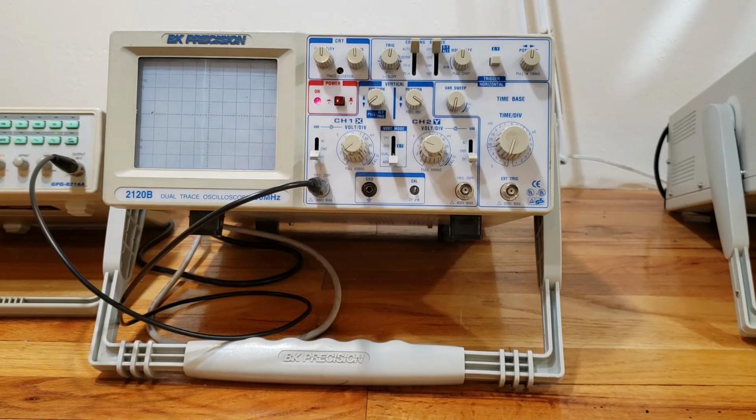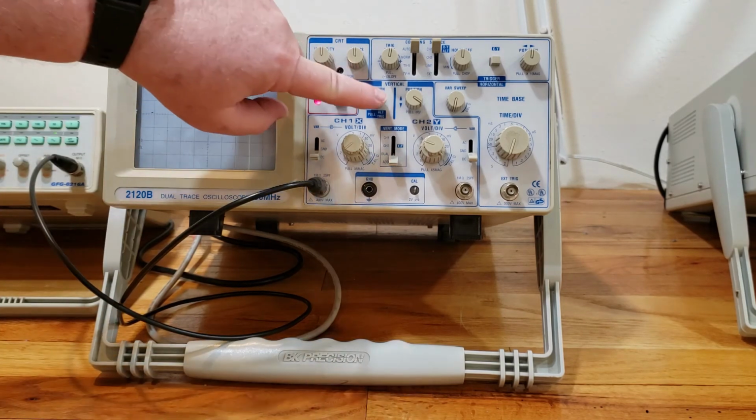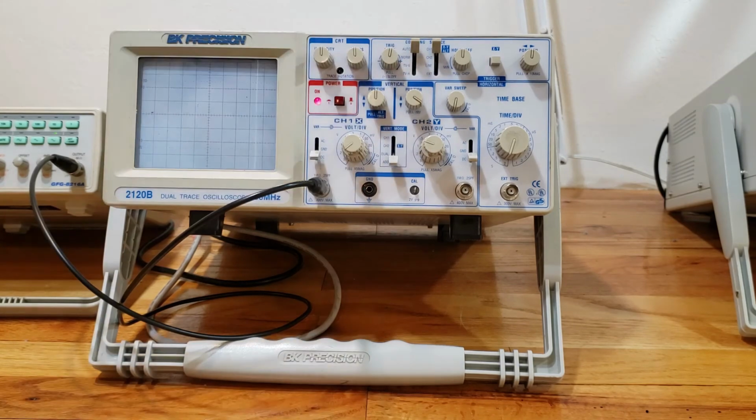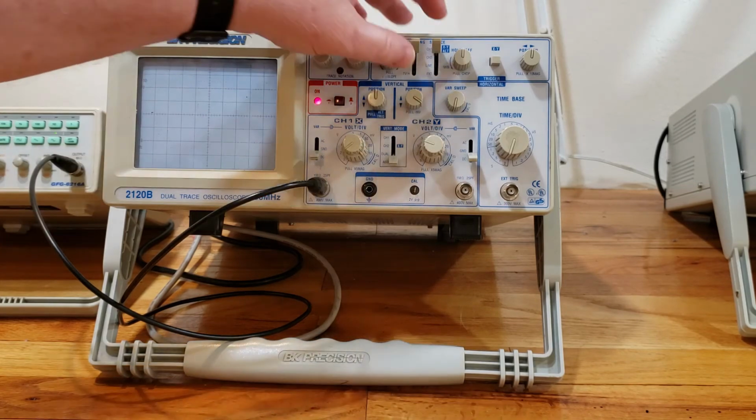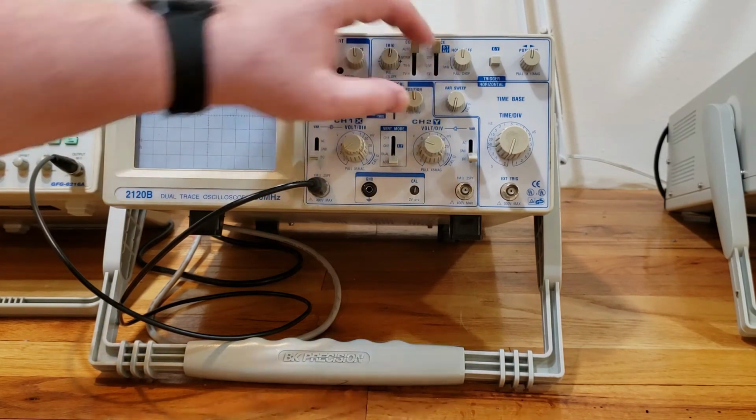Middle row, of course the power button, we're generally going to have that on, right? That would bring us to the vertical position knob for channel 1. Again, I'm going to do two things to the vertical position knob. Can you guess what those two things are? Yes, indeed. Pushed in and centered. Now, even though I'm not using channel 2, I'm going to set it up as though I am. So that means the vertical position knob, two things, pushed in and centered.